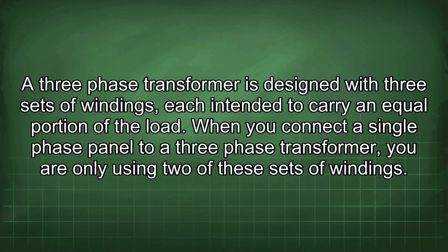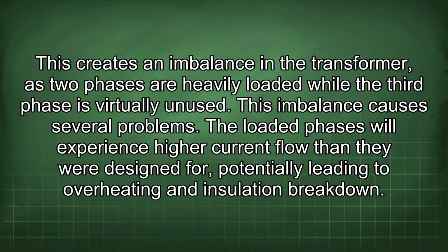A three-phase transformer is designed with three sets of windings, each intended to carry an equal portion of the load. When you connect a single-phase panel to a three-phase transformer, you are only using two of these sets of windings. This creates an imbalance in the transformer, as two phases are heavily loaded while the third phase is virtually unused. This imbalance causes several problems. The loaded phases will experience higher current flow than they were designed for, potentially leading to overheating and insulation breakdown.